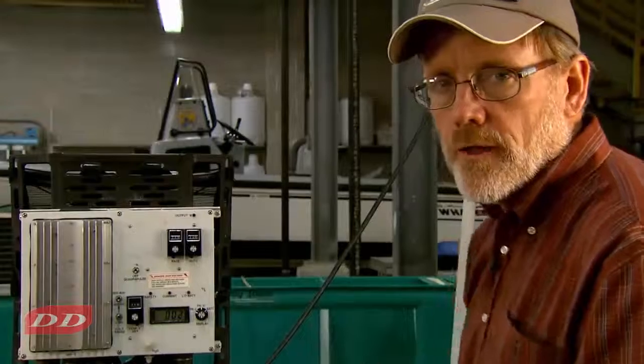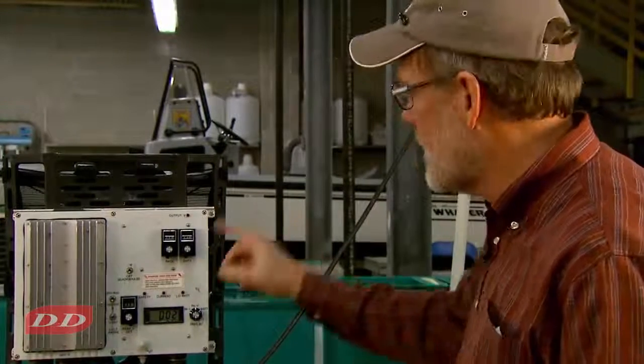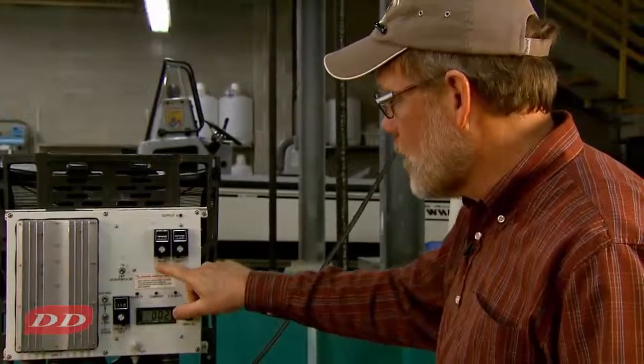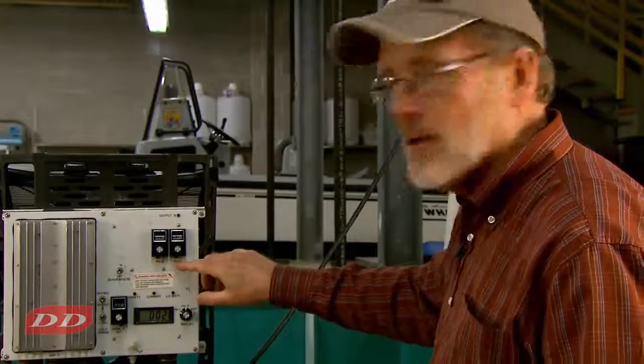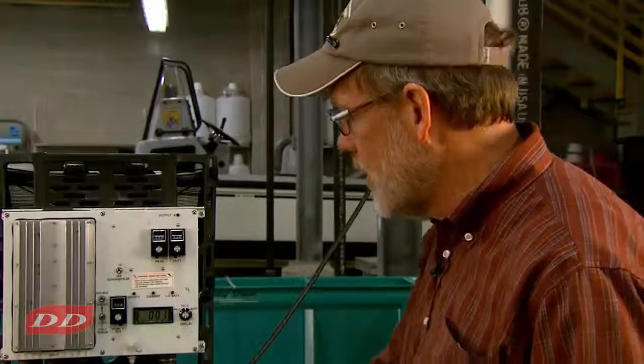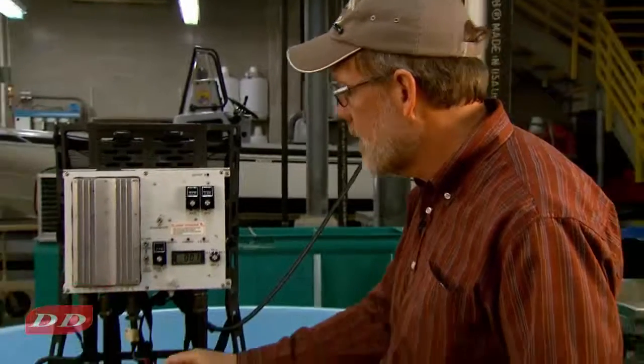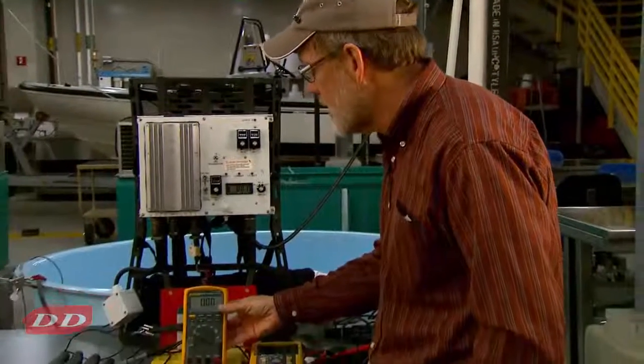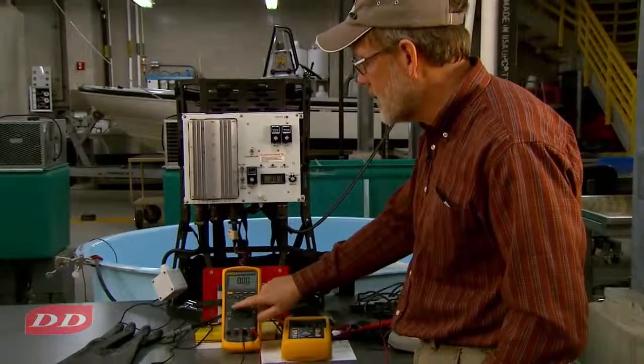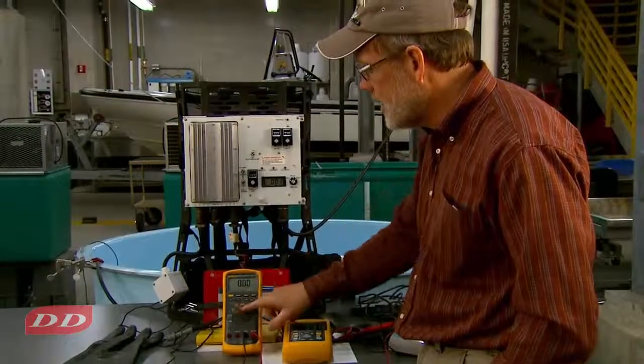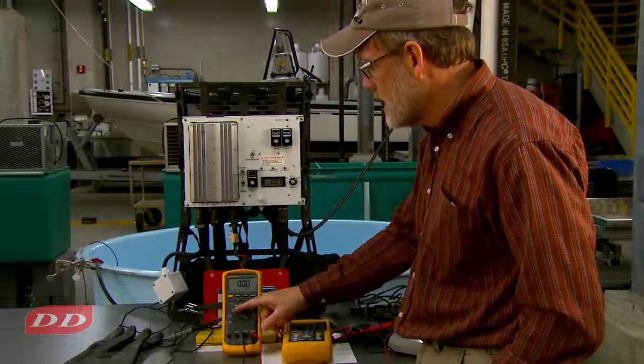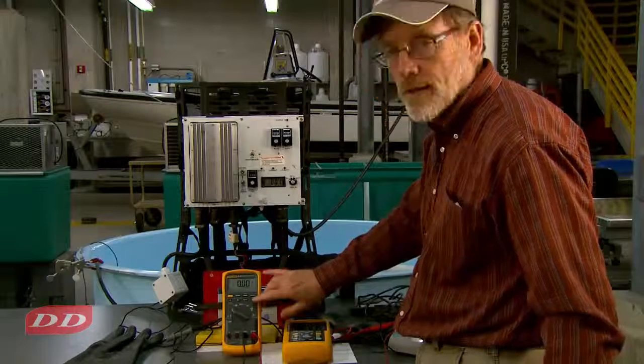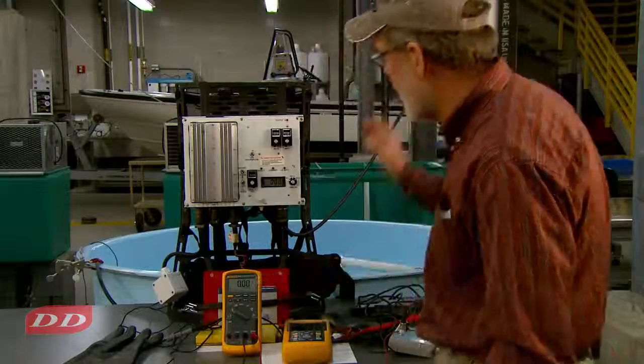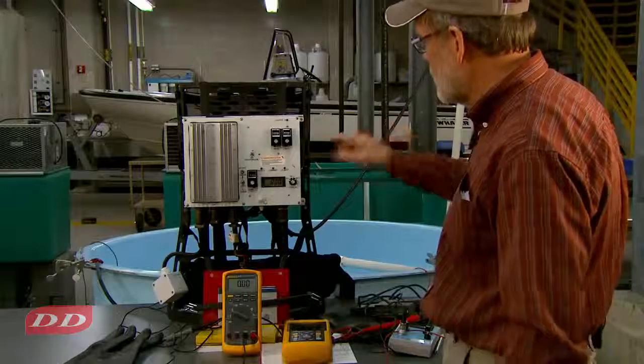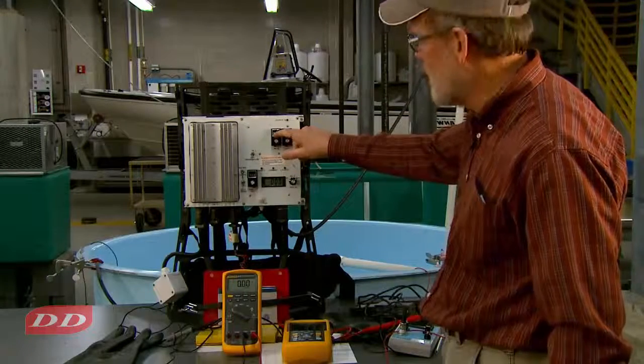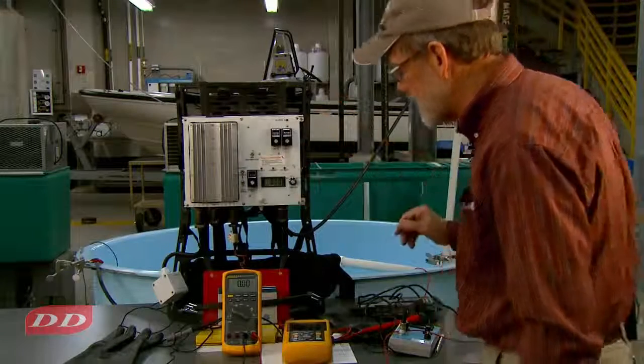Okay, two other controls that we can check the calibration on for this unit are rate, or frequency, and duty cycle. So I have the multimeter set here to frequency, and that was basically done by setting this dial knob to DC volts and pressing the Hertz button here, and that gave me Hertz. I'll apply electricity. We have a setting of 60 Hertz and 24% duty cycle, so let's see how close we get.